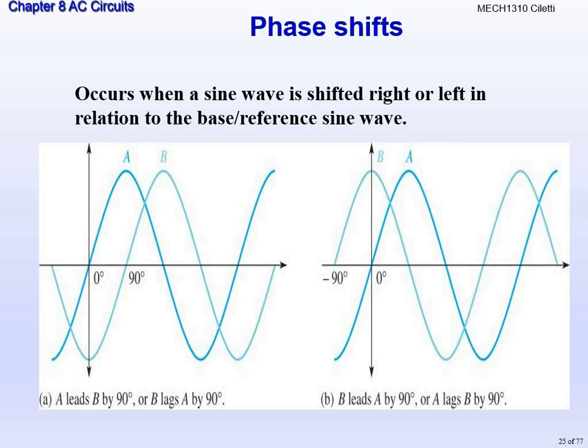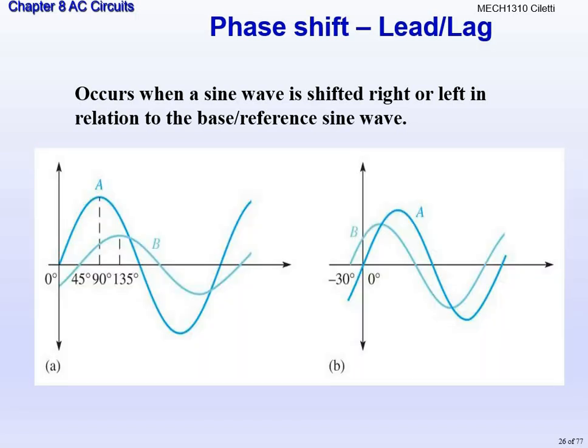So like the dryer at your house, you have a different plug for your dryer. What is that? Well, that's required to use 240. So are you using two phases there? No. You're using a single phase of 240 that's broken into two 120s that wires into that. So it's called split phase when we do that. It's not two phase. Just so that you guys know.